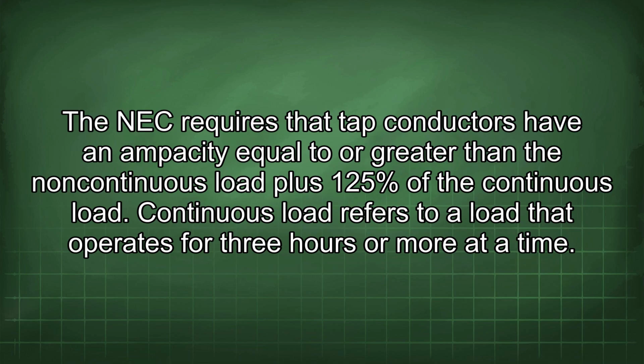The size of the tap conductors must be adequate to carry the load they will be supplying. The NEC requires that tap conductors have an ampacity equal to or greater than the non-continuous load plus 125% of the continuous load. Continuous load refers to a load that operates for 3 hours or more at a time.